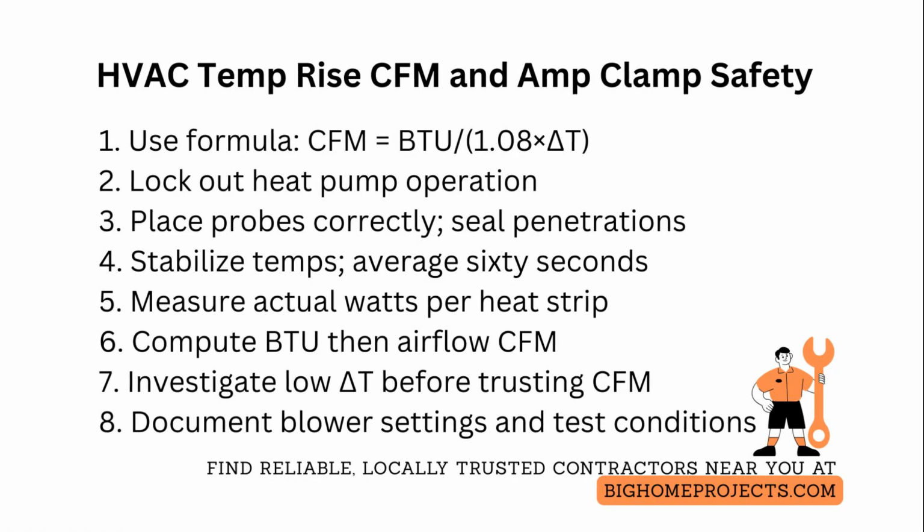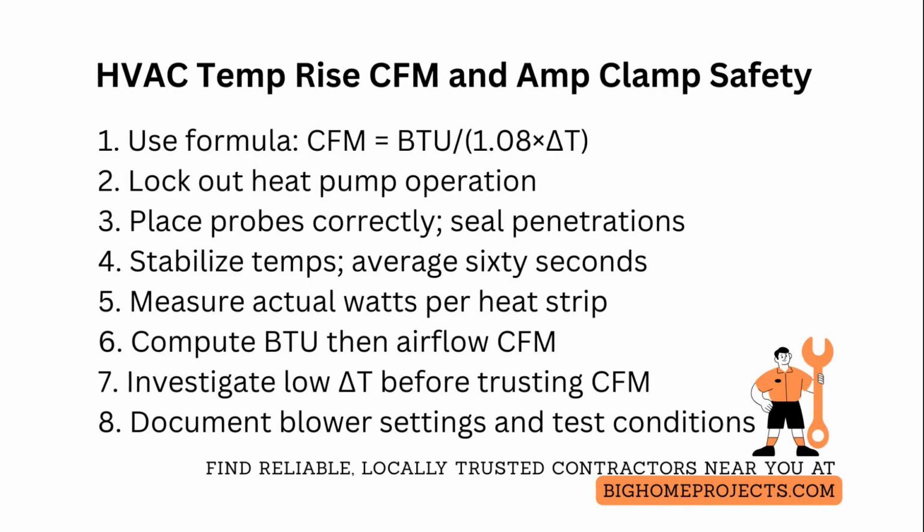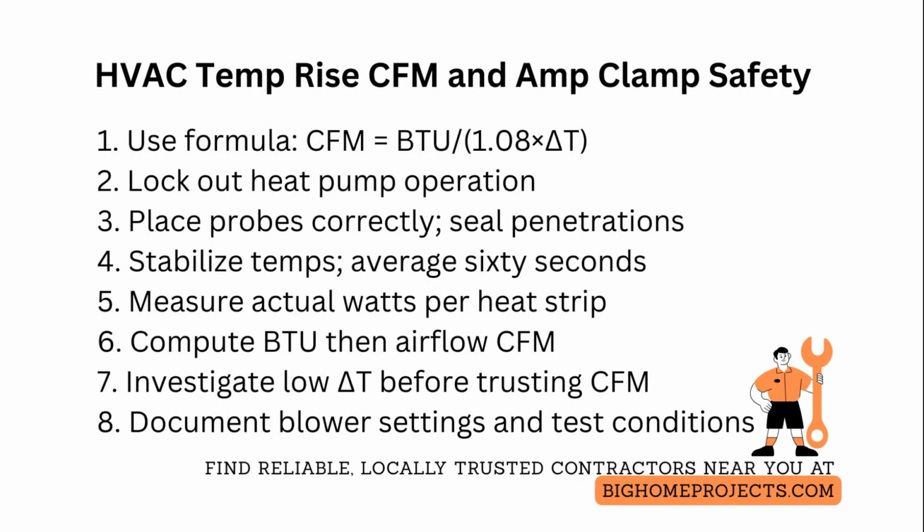Keep notes of blower tap or percent setting, filter condition, external static pressure upstream and downstream of the blower, and which strips are energized, so repeat tests are apples to apples.